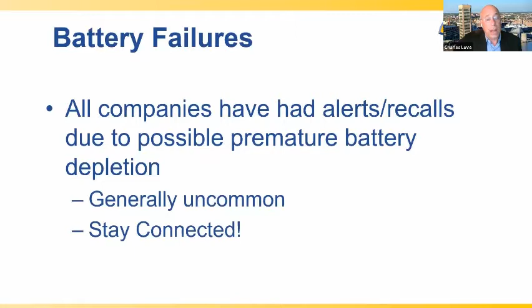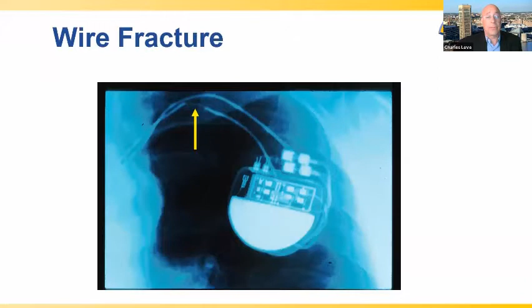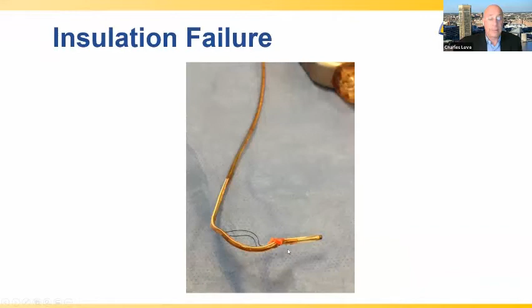This is a pacemaker wire, and you can see right under the collarbone here, there's a disruption of the wire. This can cause discontinuity and, of course, malfunction of the system. We saw one looking like this as well. Charlie showed a very similar picture where the insulation has failed and these conductive coils have eroded through the insulation. This can create noise and, again, failure of the wire.